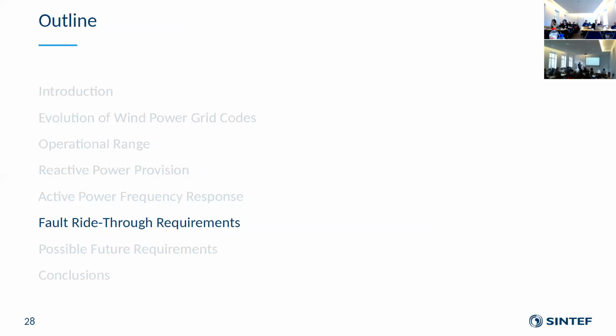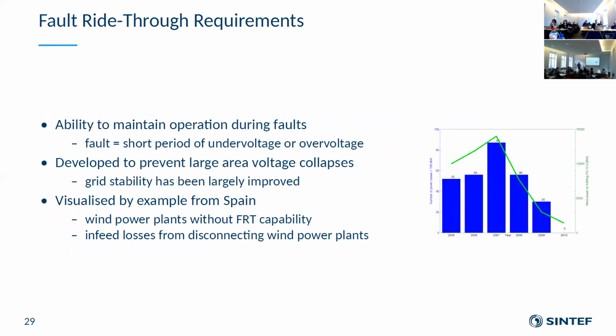Next is fault ride-through, as shown with the voltage dip that caused the problem. The fault ride-through requirement tells you that even though you have this deviation of the voltage, if it's just for a short time, you have to be able to ignore it and keep operating. This is what did not work with the wind farm in that example. This requirement was developed to actually prevent this from happening, and even though it doesn't always work, it works often and has really improved grid stability a lot.